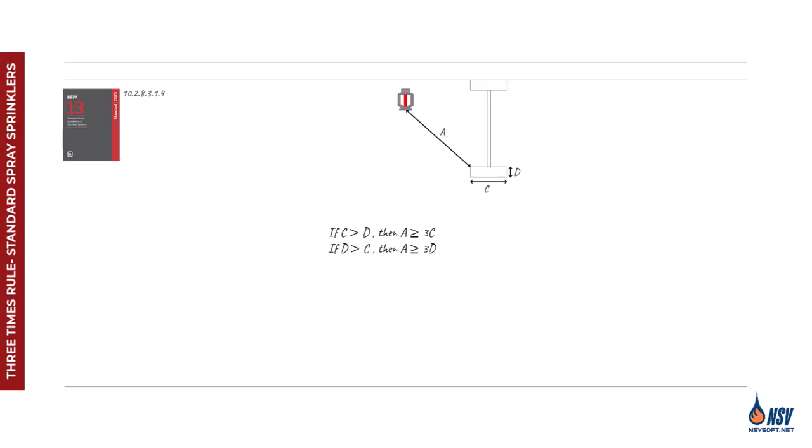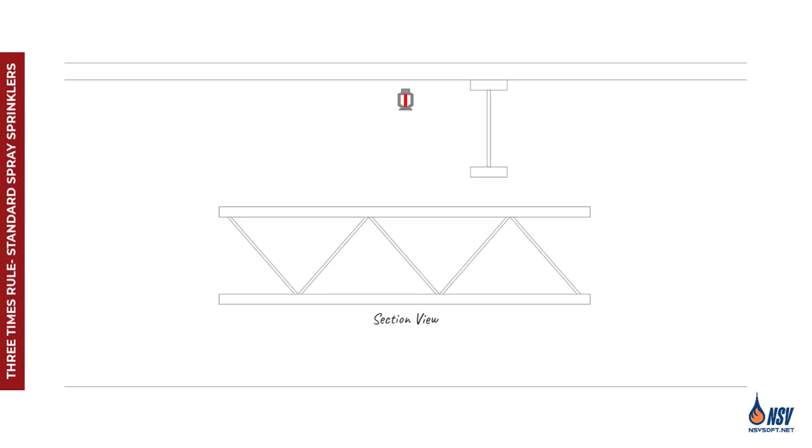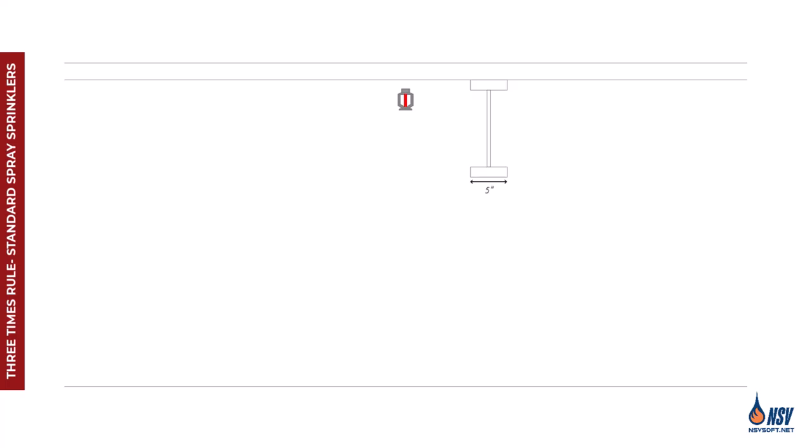This ensures that the spray pattern remains effective and isn't compromised by the presence of the obstruction. For example, consider an open web joist with openings that make up at least 70% of the cross-sectional area, allowing water to pass on both sides of the bottom flange. If the joist's width is 5 inches and the depth of the flange is 1 inch, the largest dimension is 5 inches. Applying the 3x rule, the sprinkler shall be installed at a minimum distance of 15 inches from the bottom flange.